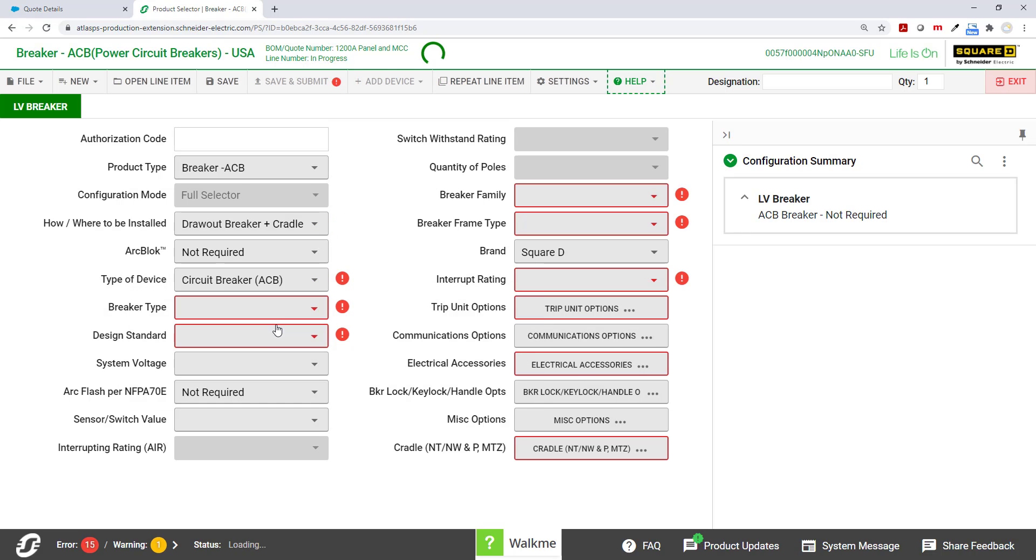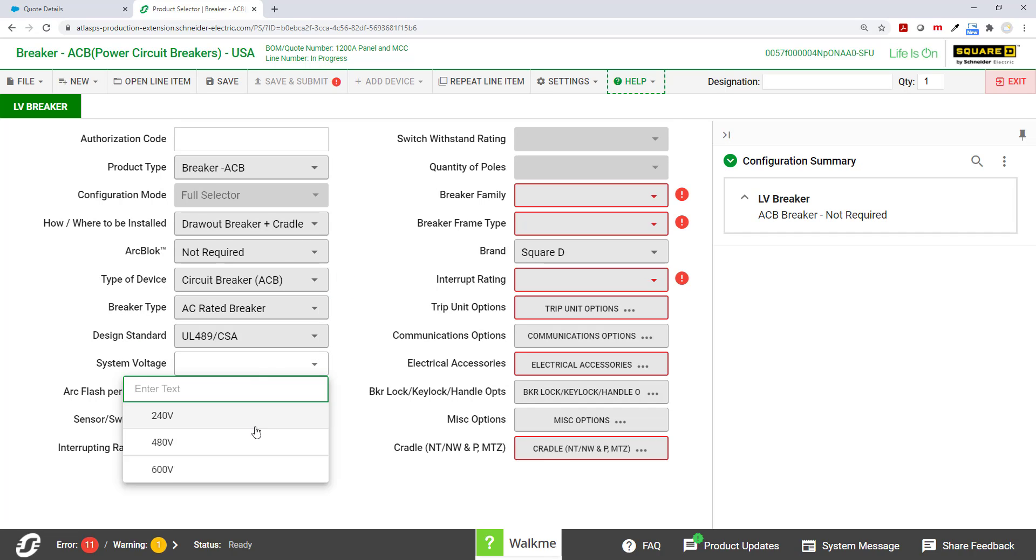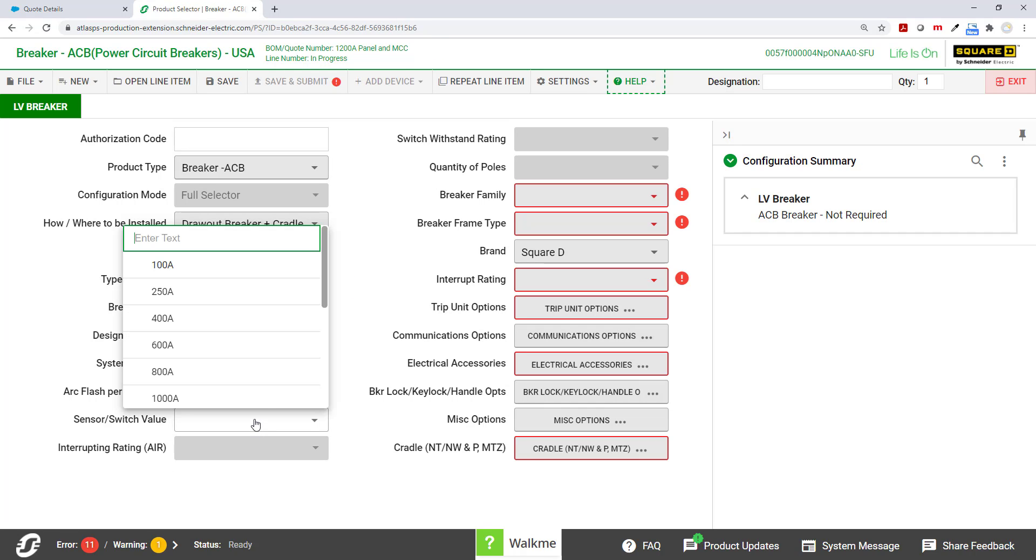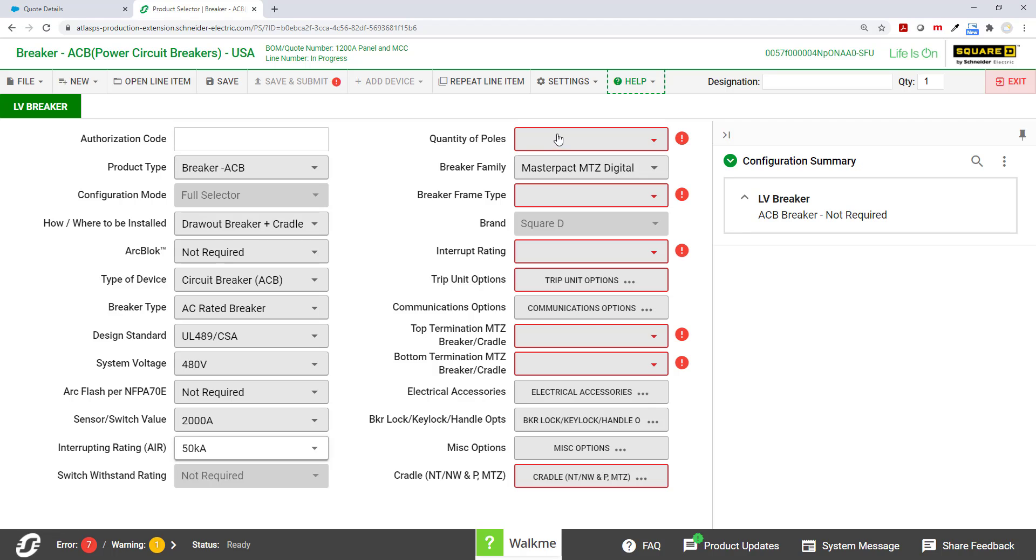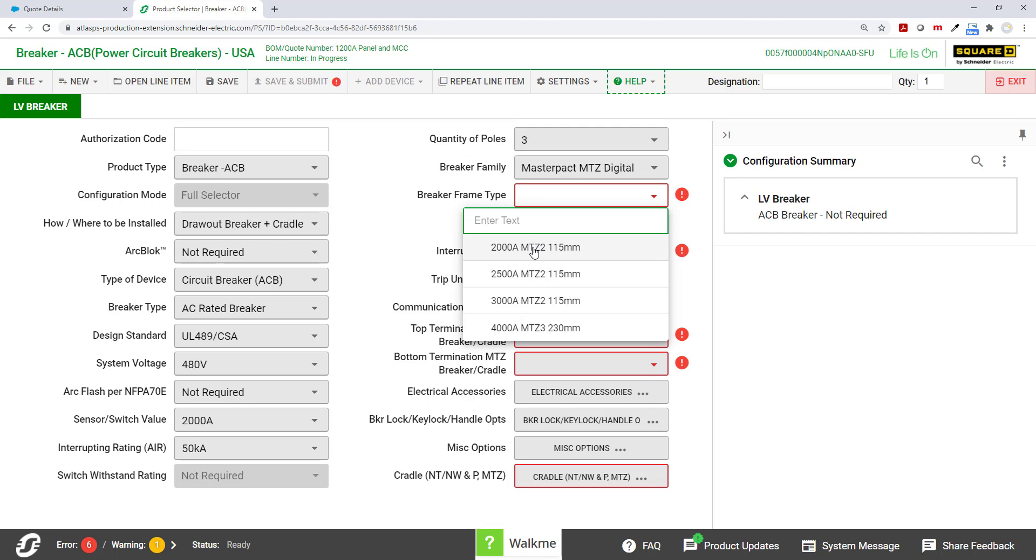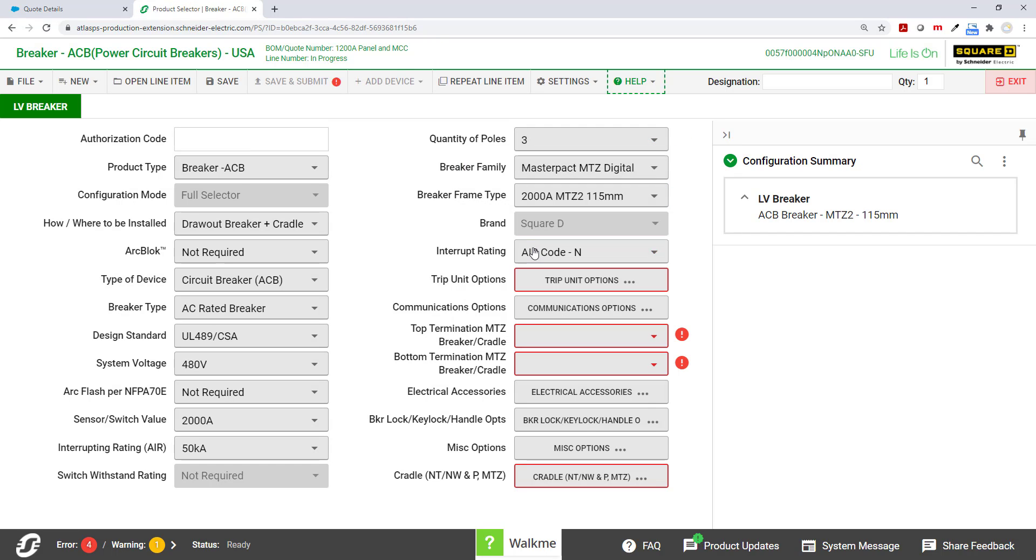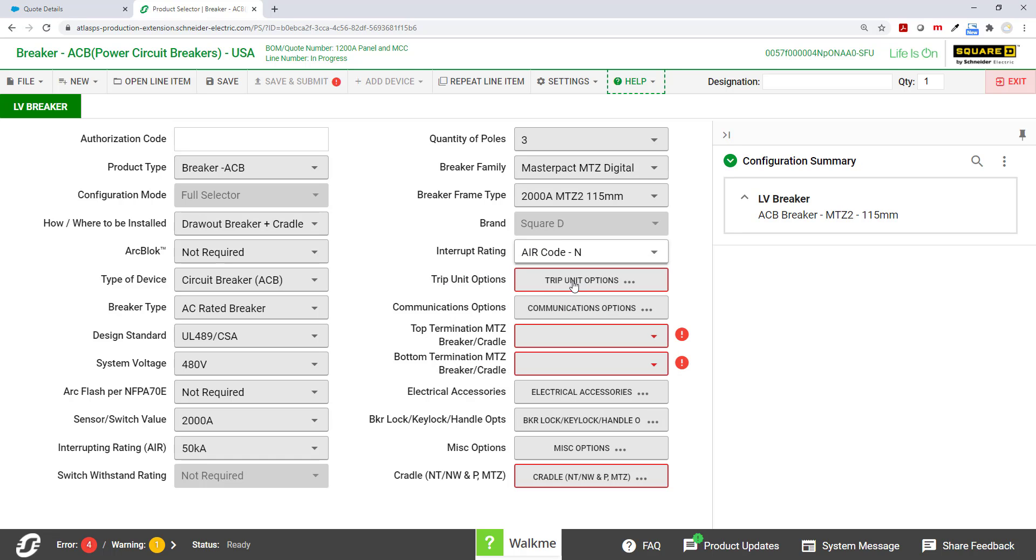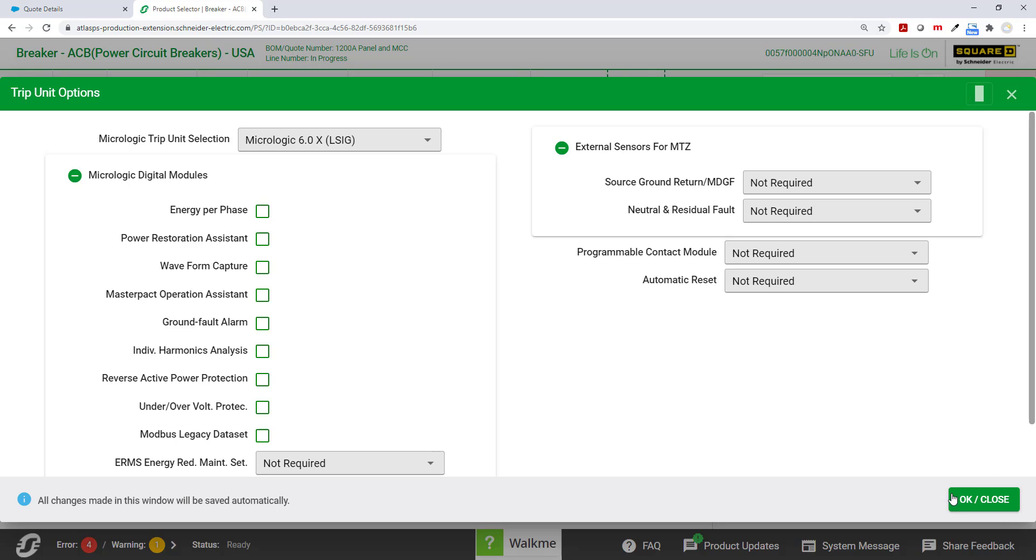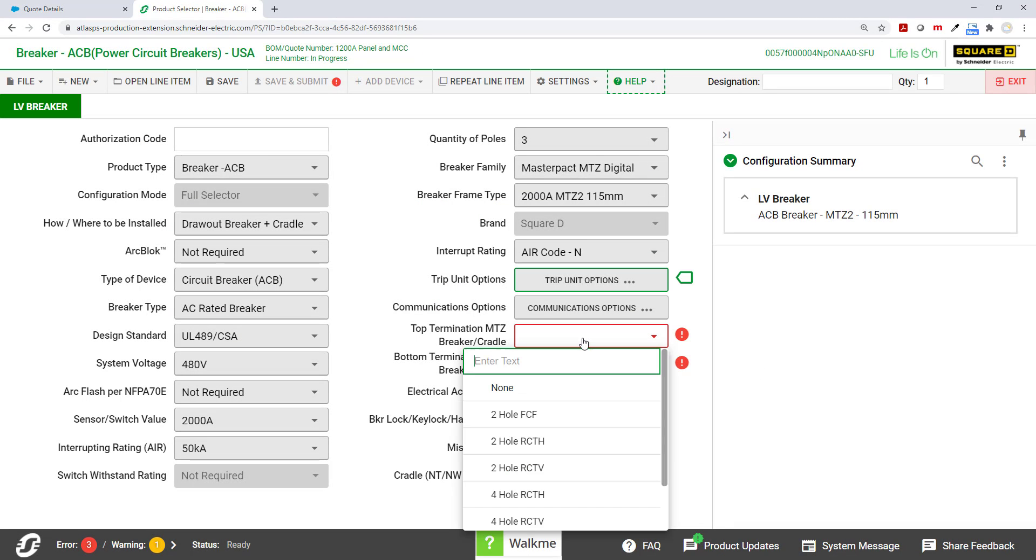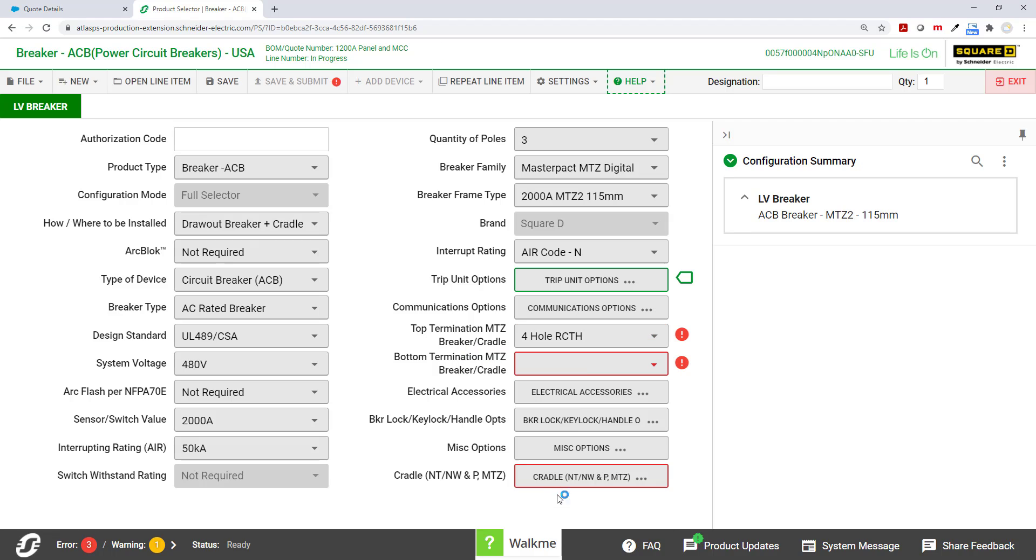It's going to be ACB, AC rated, 480 volts. And I'm going to put this as 2000 amp breaker. Three pole, make sure it's MTZ. And I think I'll do an LSIG. And we'll continue through just creating the rest of those breaker options.